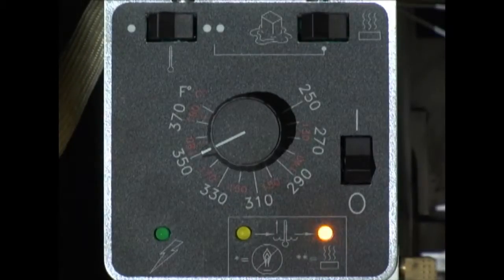This control also monitors the closed condition of the drain valve. If the valve is detected open, the control assumes that the vat has been drained and the heating control is suspended. The heat feedback indicator will flash 7 times, pause, and repeat.